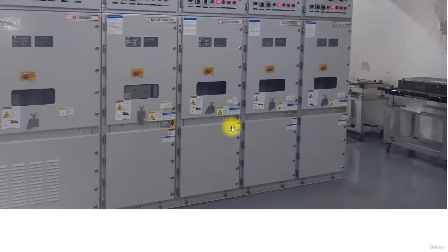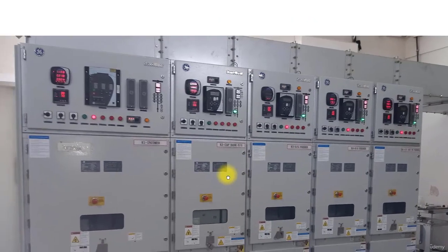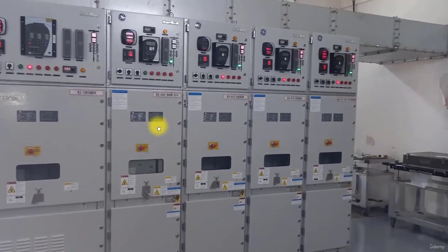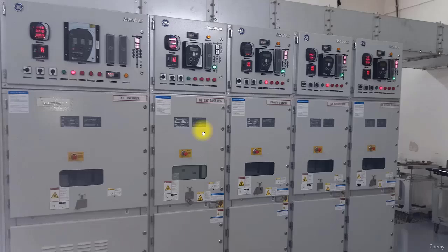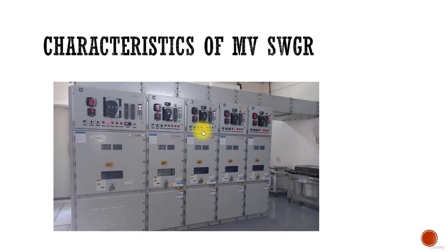Further downside, the VTs are placed, earthing switch access is also available at the downside, and at the back side of it the cable is connected. And if you see further, you can see the bus bar arrangement is also inside this. So switchgear is the combination of all protection, control, and the high voltage equipment. So we are combining all these things in a single package. However, they have separate compartments that we will learn later, but we are combining all this, and the reason is that the ultimate aim is to make an optimized design and control the cost.